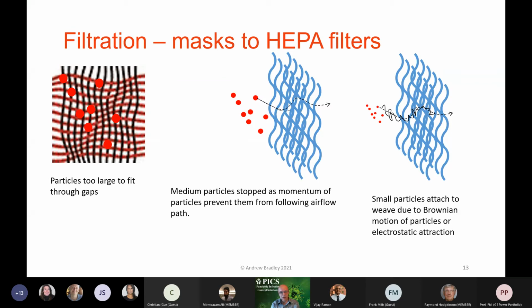Filters work by larger particles being physically blocked from passing through - they can't fit through the gaps. With medium-sized particles, as air flows through, it has to go through a fairly convoluted path, and by momentum the particles don't follow exactly that path, so they collide with the surface of the fabric and attach to it. So even though they're smaller than the holes, they won't actually get through. With very small particles, Brownian motion or electrostatic attraction makes sure they touch the surface of the weave and get stuck there.